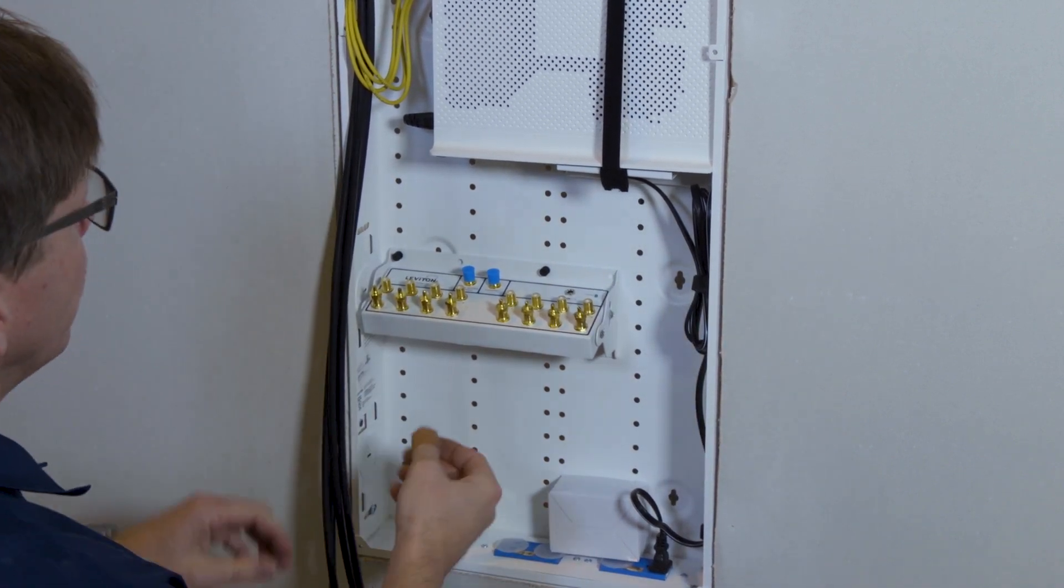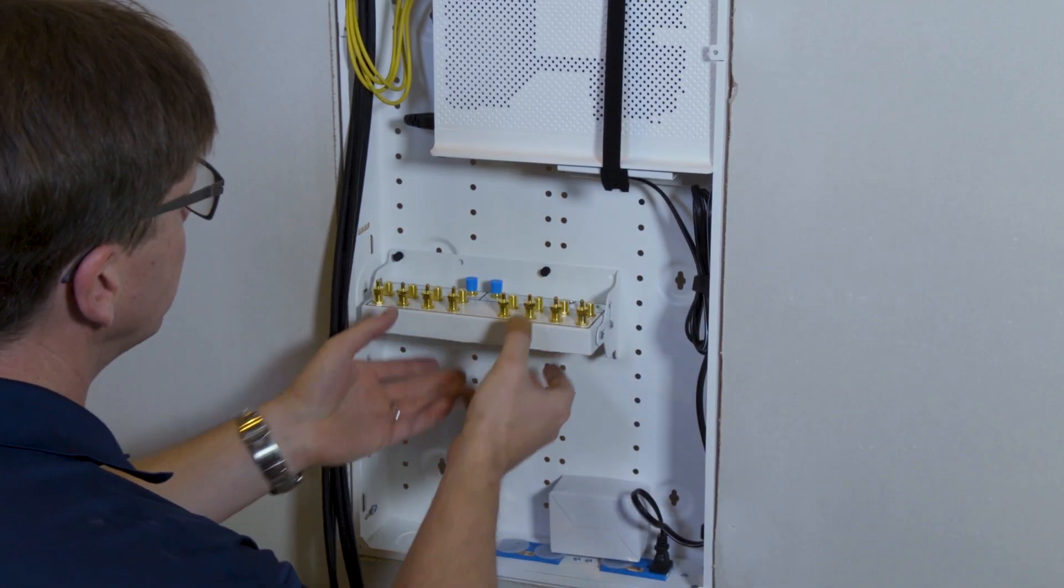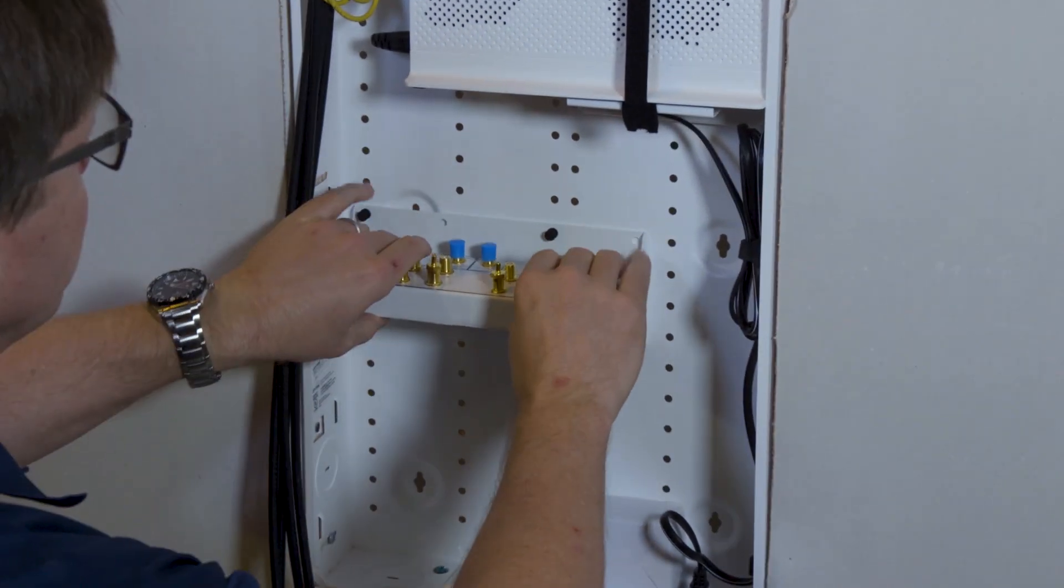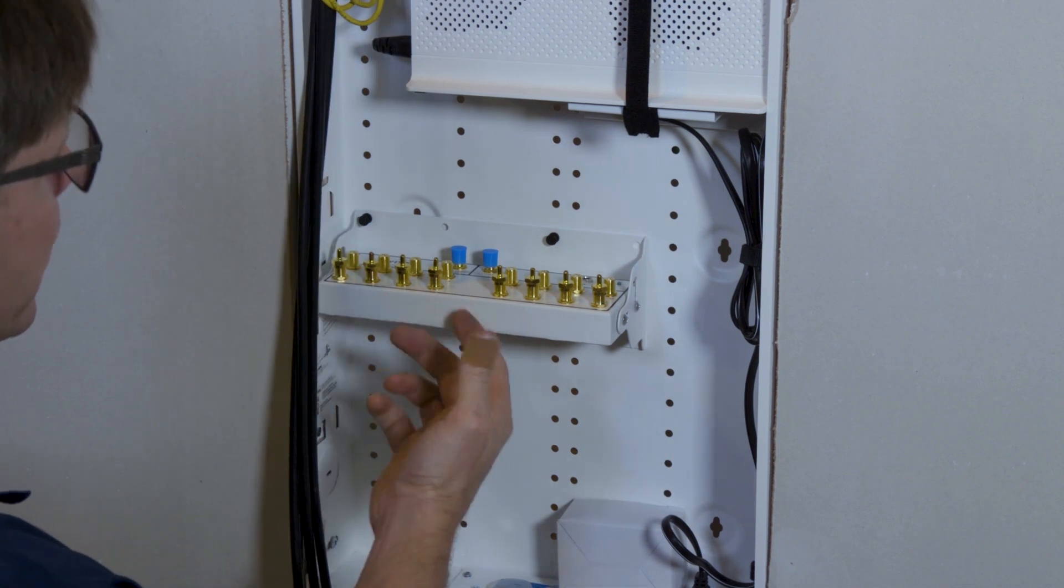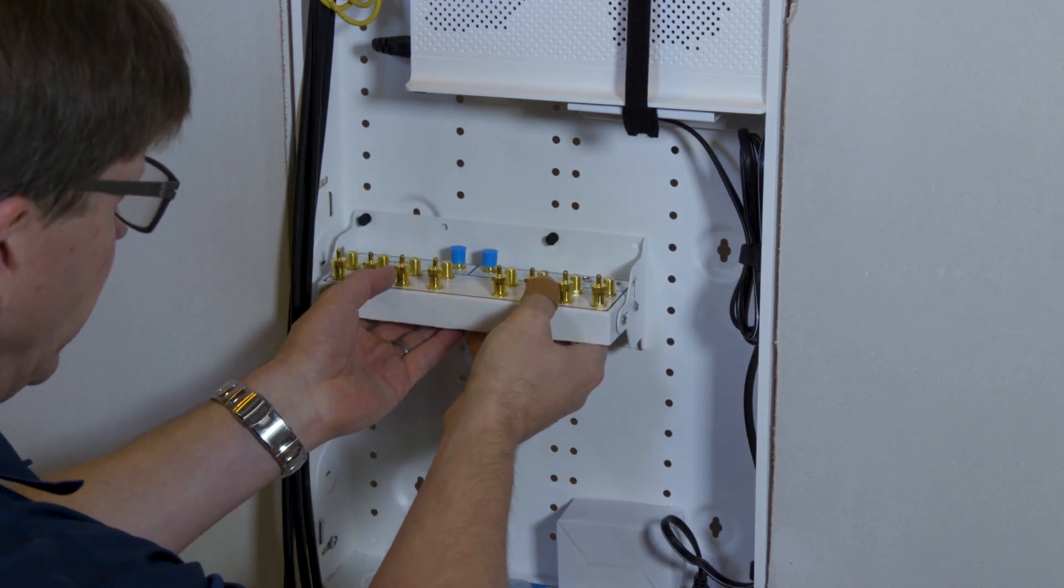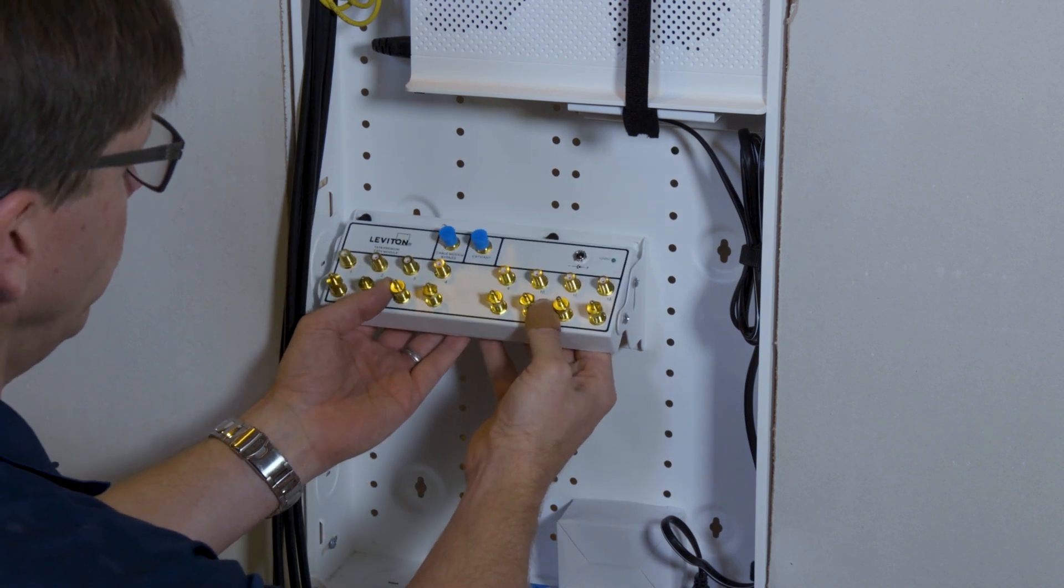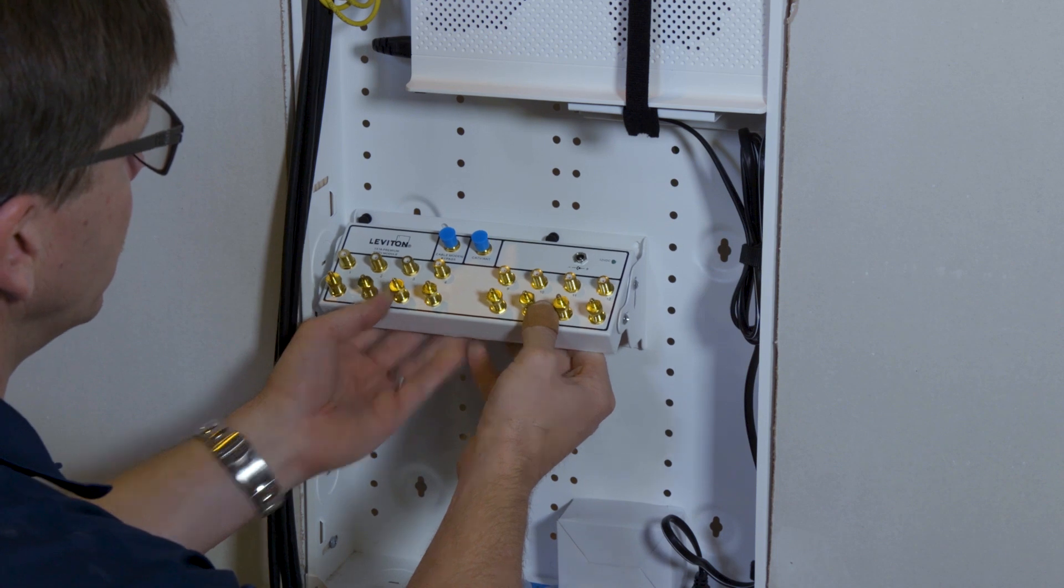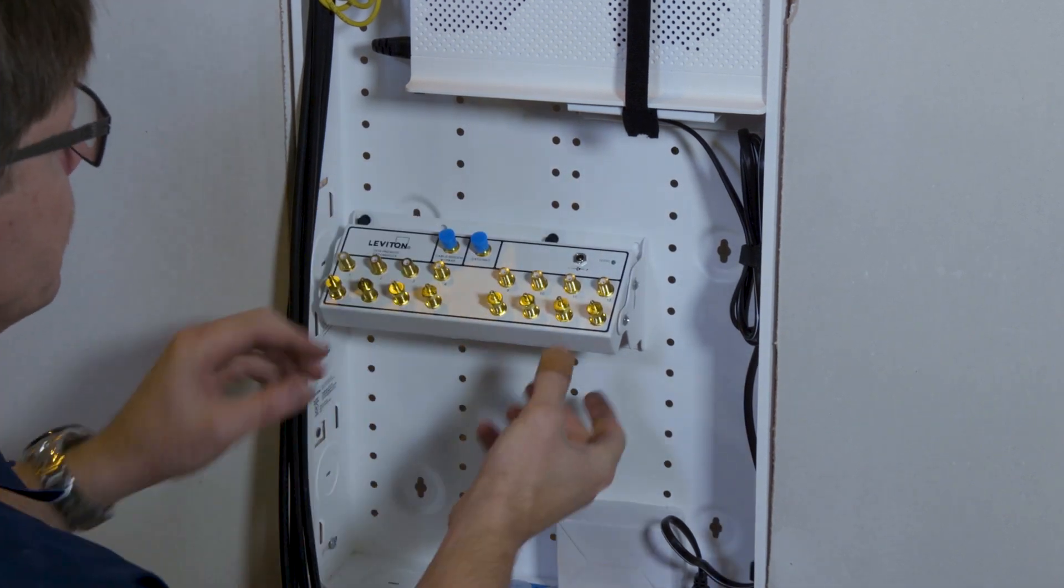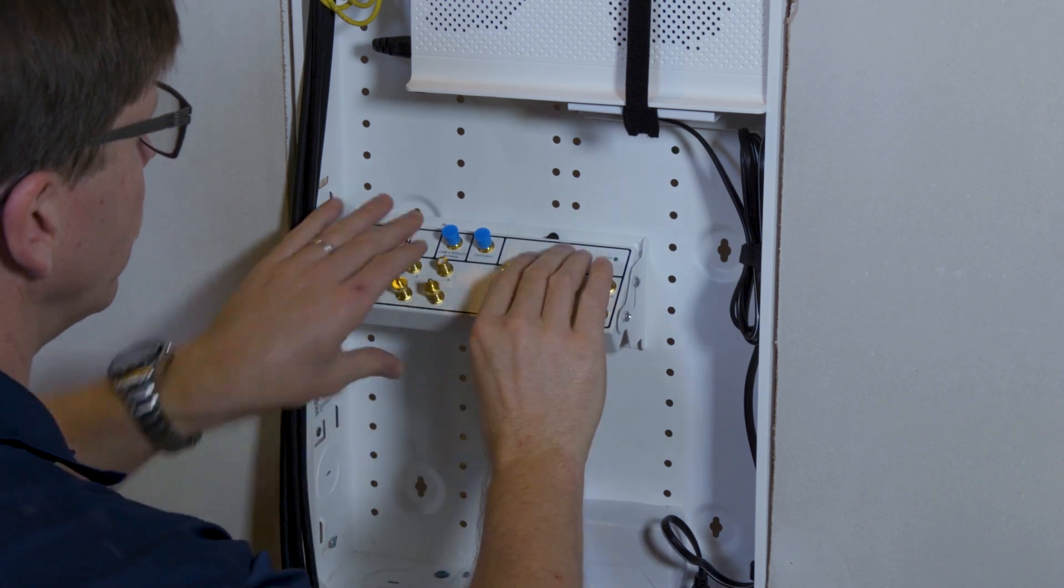This module has a tilt adjustment to it. Normal operation is here with your cables terminated. In order to make it easier to install the cables, this module can be tilted out and pulled towards you. When you pull it towards you, it locks in place so that you can do your termination. When you're done, push in and then rotate.